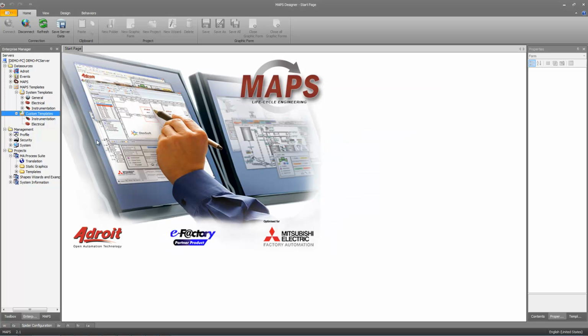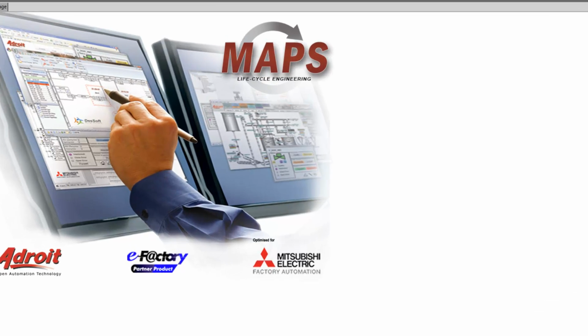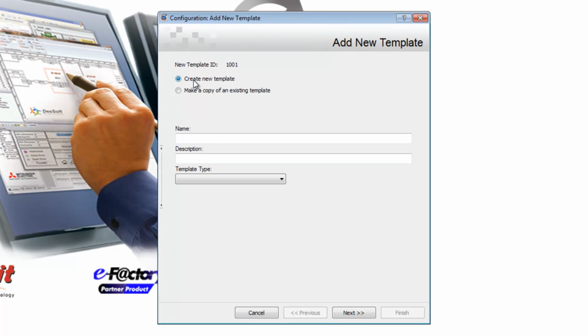Okay, so now I've defined what the agent would look like. The next thing is I'm now going to add my template. So first of all, I'm going to create a new template. You'll see that the template ID is 1001 because all custom agents will start from 1000 and above. So now we need to call this sample start, and we give it a description. And then we specify, does this fall into the category of electrical or instrumentation? So I'm just going to put it into instrumentation for the moment.